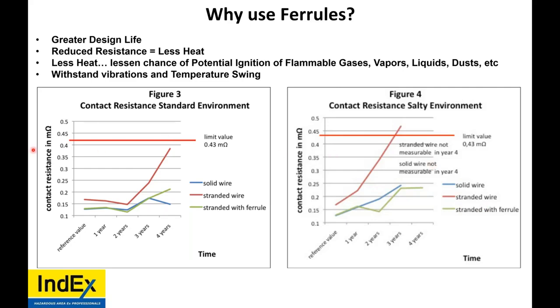Okay, good. Now, why the use of ferrules? Well, this has been done by the manufacturers, by Weidmuller, by Phoenix. But why the use of ferrules? Well, greater design life. Reduced resistance equals less heat, less chance for ignition in a hazardous area. Less heat, once again, less potential ignition of gases, vapors, liquids, or dust. Also, they withstand vibrations and temperature swing.